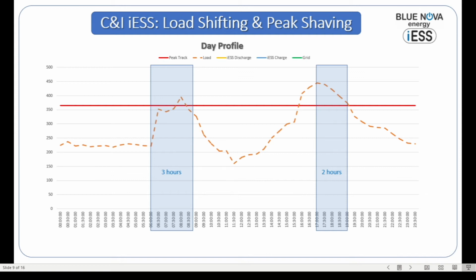So the principle of operation is quite simple. We would like to have a controlled discharge during these peak periods, and then also to ensure that the peak that one sees here, just to the left of the second discharge period, that is sort of preempting the peak tariff period, one would like to clip that peak as well. So that is the specific area that I'm talking about there. If one implements the charge and discharge profiles as depicted by the yellow and blue lines at the bottom of the graph, one can then see the resultant energy demand from the grid, which is the green line.